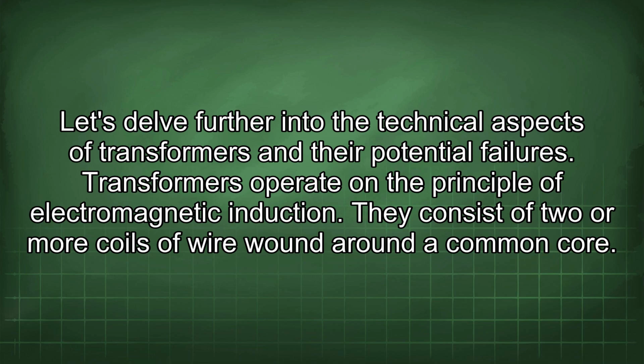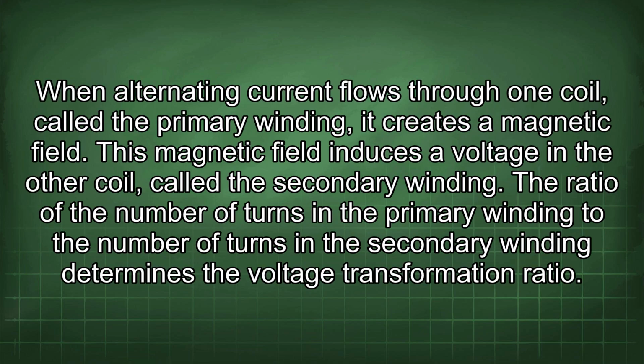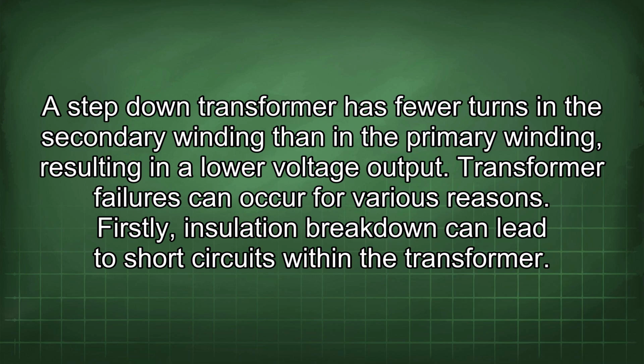Transformers operate on the principle of electromagnetic induction. They consist of two or more coils of wire wound around a common core. When alternating current flows through one coil, called the primary winding, it creates a magnetic field. This magnetic field induces a voltage in the other coil, called the secondary winding. The ratio of the number of turns in the primary winding to the number of turns in the secondary winding determines the voltage transformation ratio. A step-down transformer has fewer turns in the secondary winding than in the primary winding, resulting in a lower voltage output. Transformer failures can occur for various reasons.